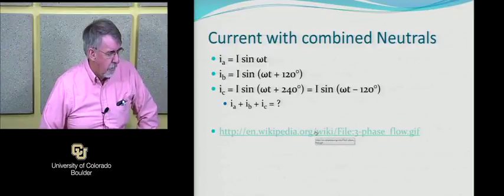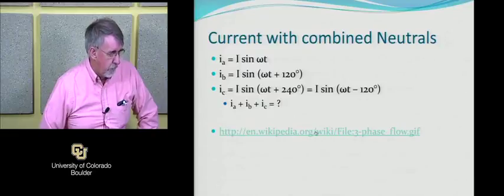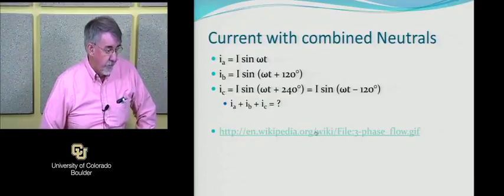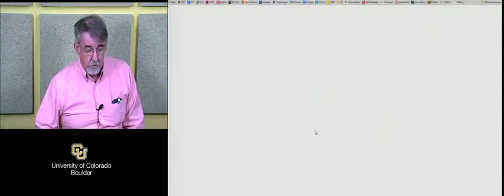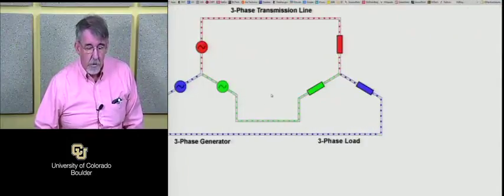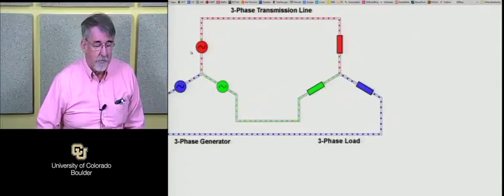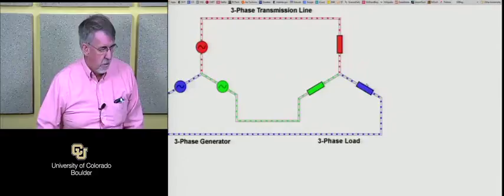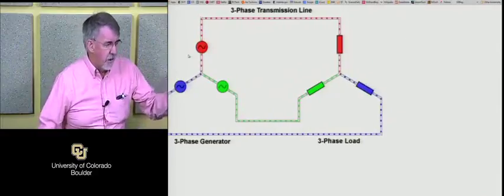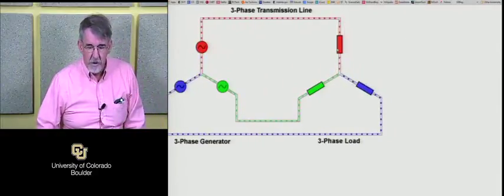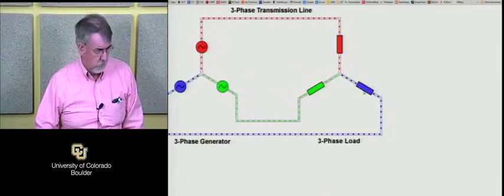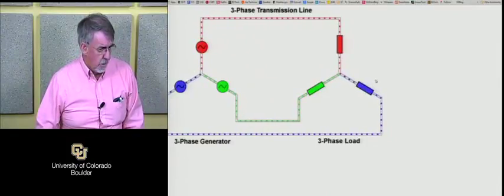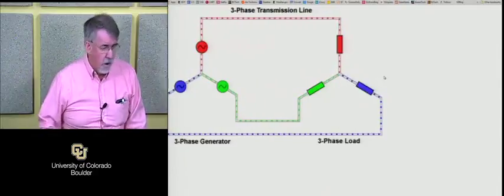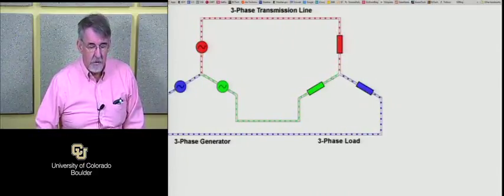It's when the 3 voltage phases are not all the same voltage line to ground—when it's not balanced, that's what that's called. So you've got 3 generators over here and 3 loads over here. If the generators are identical but the loads are not identical, you get an unbalanced situation where the current in each of the legs is different.